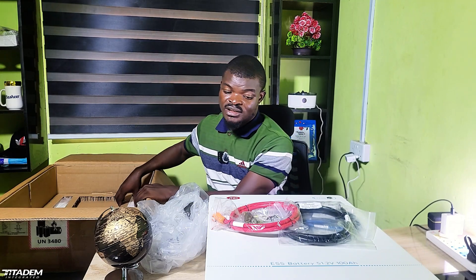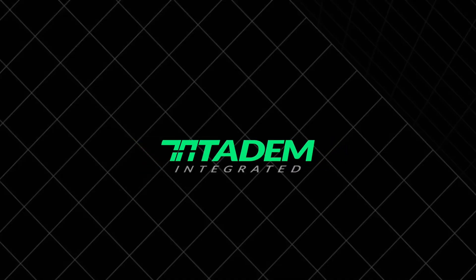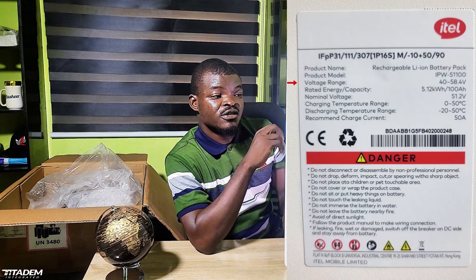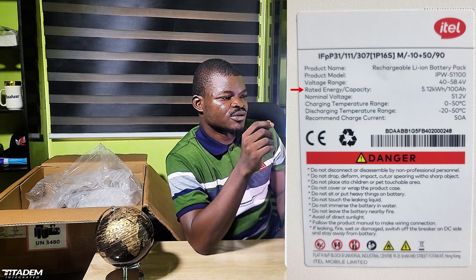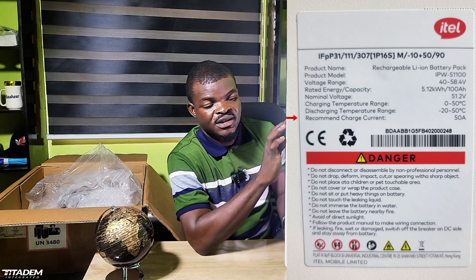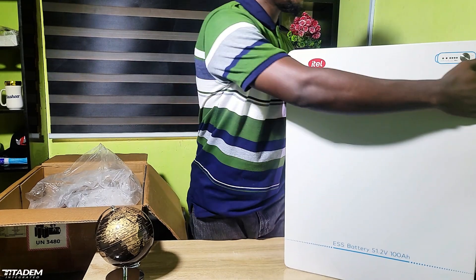So those are the things that came with the battery. Now let's check the specifications. At the front, we have the power on/off button and the indicator LEDs. On the nameplate: product name, voltage range 40V to 58.4V, rated energy 5 kilowatt-hours, 48V battery, nominal voltage 51.2V. Then the operating temperature, start temperature, and recommended charge current of 50 amps.